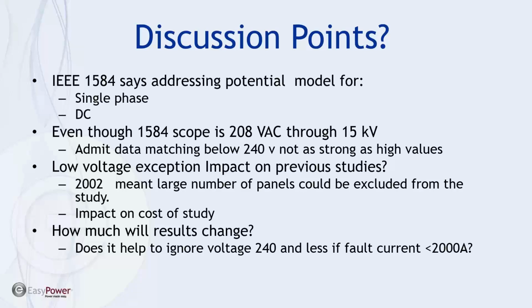Now, even though the current scope of 1584 is 208 volts through 15,000 volts, there is some acknowledgement that the data matching for the model below 240 volts is not quite as strong as the higher end of the voltage spectrum. And so there's some wiggle room, if you will, and that's evidenced by the low voltage discussion I just had in the previous slide. The fact that the low voltage exception now has been removed, does the client benefit from including all these panels that were ignored the first time through, and what's the cost impact of a renewal or an update of his previous study? And then how much will it really change the results of the overall system analysis?